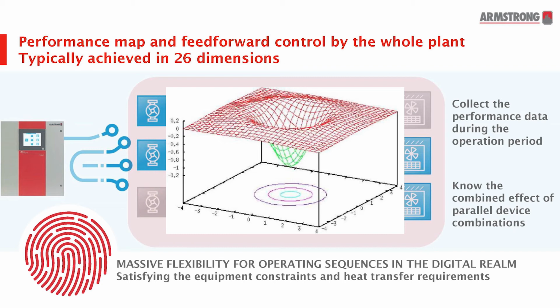They all include a power measurement, a power reading. We add up those powers for all those possible combinations, sort them, and get the one that uses the least power. That's the operating condition we're going to apply to the plant in terms of which pumps to run, which chillers to run, which cooling towers to run, what's the fan speed, what's the chilled water supply temperature, etc. So it's a whole new way of leveraging a digitalized capability to optimize the performance of the plant regardless of the condition of our equipment.